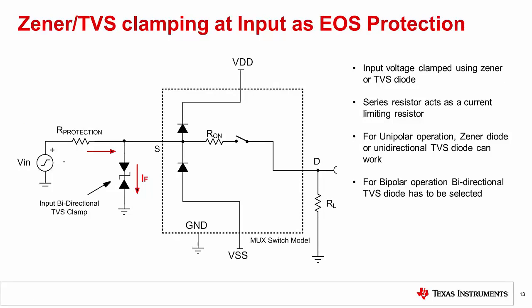A solution for the case where the overvoltage fault occurs on an off channel is to use a Zener or TVS diode to clamp the input channel within the absolute maximum input range. A unidirectional TVS diode is normally used for a single supply configuration, and a bidirectional TVS diode is used for a bipolar supply. The clamping voltage is selected so that the input does not exceed VDD or VSS supply to the device. A series resistor acts as a current limiting resistor. Take care to understand the parasitic capacitance and leakage currents of the input clamp to ensure system performance is not impacted.